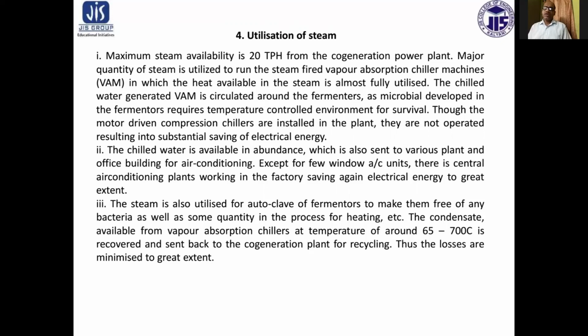Utilization of steam. Maximum steam availability is 20 tons per hour from the cogeneration power plant. Major quantity of steam is utilized to run the steam fired vapor absorption chiller machine, in which the heat available in the steam is almost fully utilized. The chilled water generated by the VAM is circulated around the fermenters, as microbes developed in the fermenters require a temperature controlled environment for survival. Though the motor driven compressor chillers are installed in the plant, they do not operate, resulting in substantial savings of electrical energy.